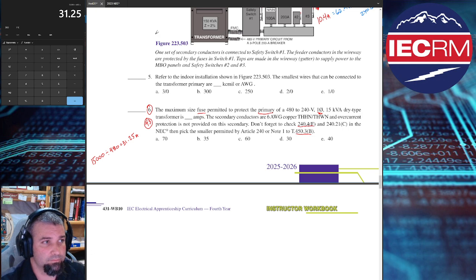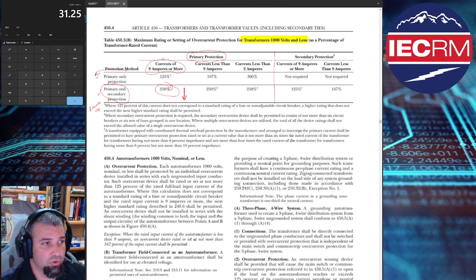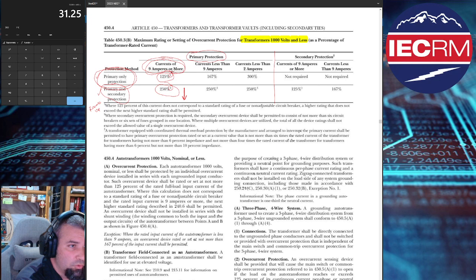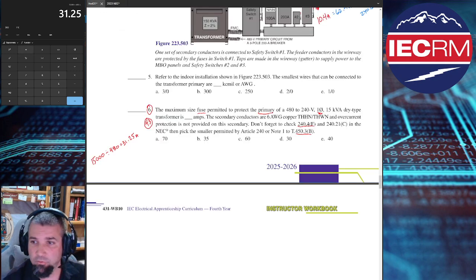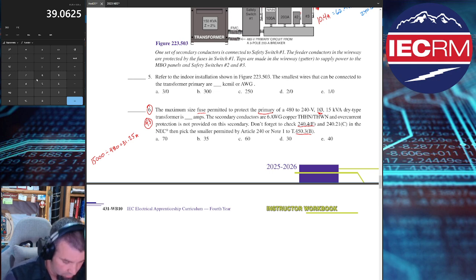Now, we are talking about a fuse. Let's take a look at this. Primary protection only. Okay, it said that specifically in there. Currents of 9 amps or more. Okay. I have 125% with a superscript 1. Remember that superscript 1 means we can round up. Lovely. So I'll take that 31.25 times 125%, 1.25. 31.25 times 1.25 equals 39.06 amps. And we said I can round up, right? I can round that up to 40 amps out of 240.6.